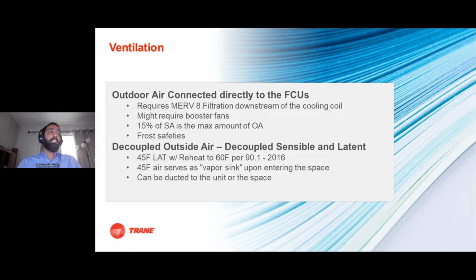And so it's important to be mindful of the frost safety. The decoupled outside air, this typically means separating the latent and the sensible load. So the sensible load is done at the VRF terminal unit in the space, and then the latent load is taken care of at an outside air machine.